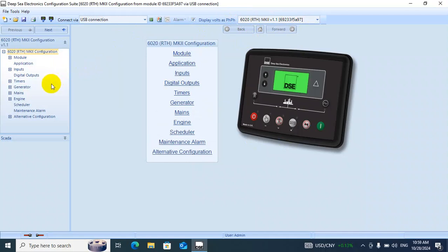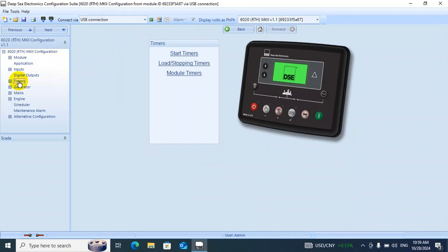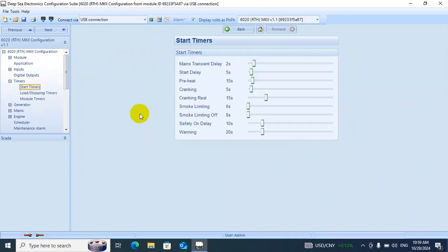You don't need to change anything, but when we want to program the module, you have to check the crank time, preheating, start delay, and mains transfer delay. You are not touching these options.